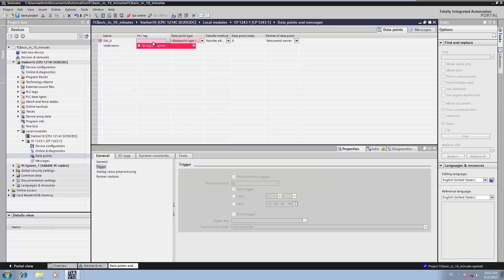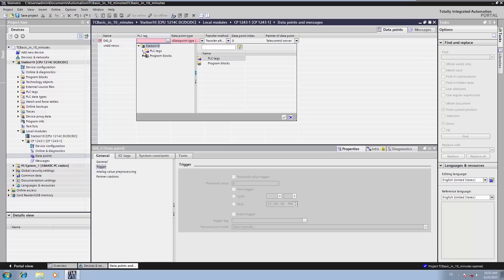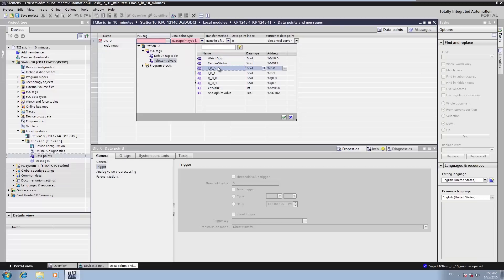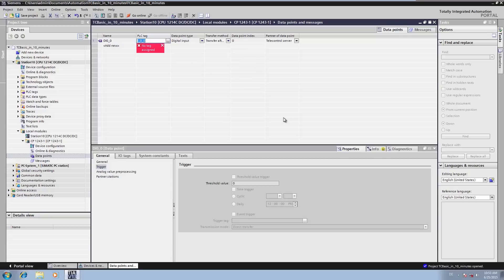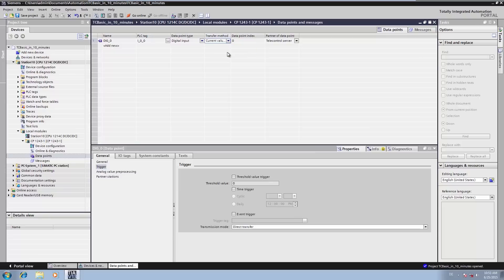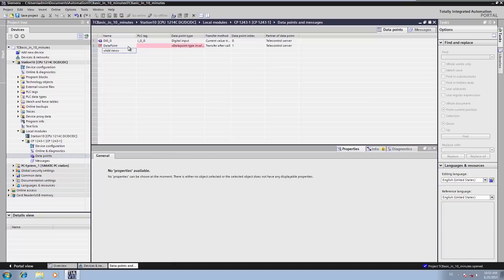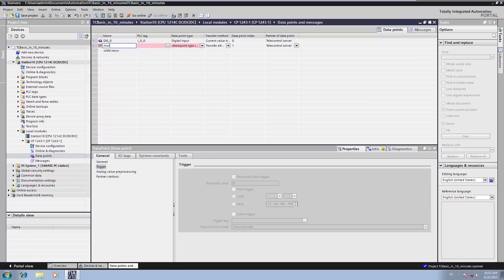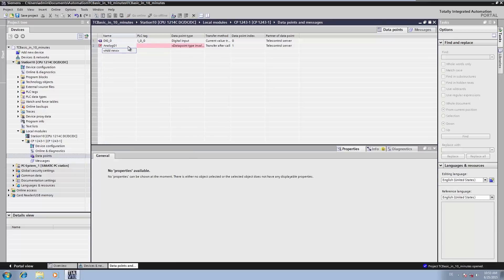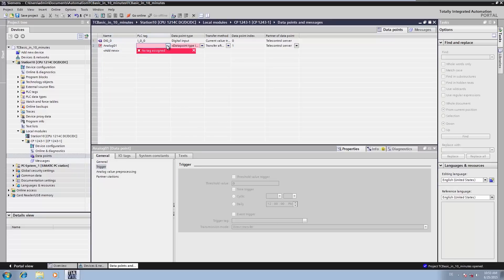We link this point directly with the input 0.0 of the CPU. Then we specify the transfer conditions to enable change evaluation and event-driven transmission of the value: current value triggered, threshold value active. To transfer the analog value, we create a data point of the type analog input. We link it to a variable with an analog value.